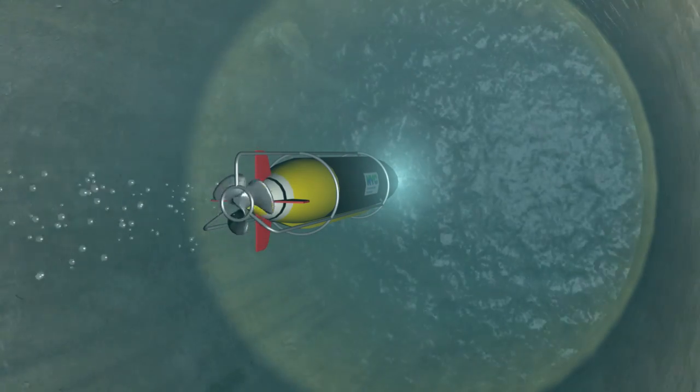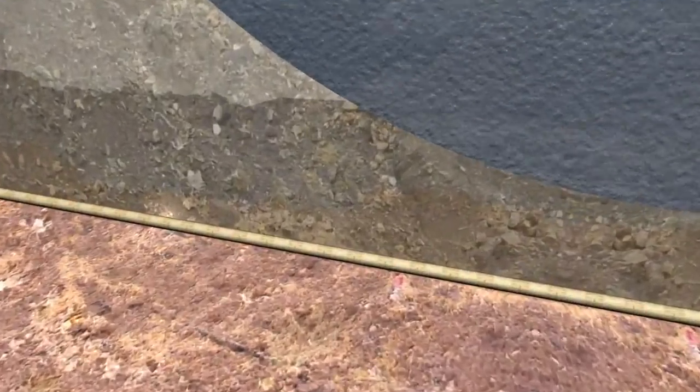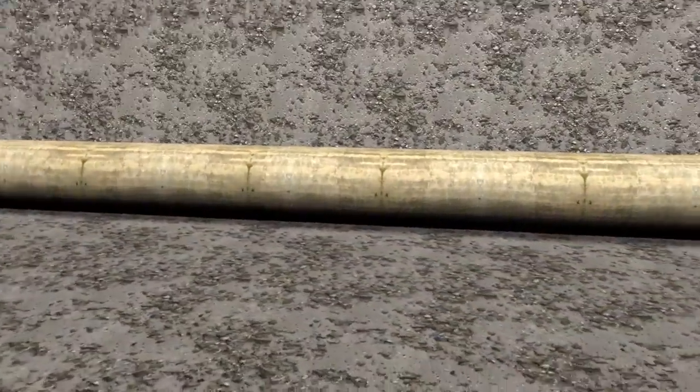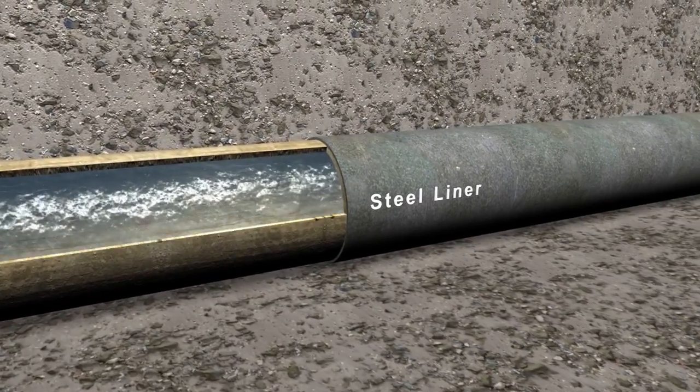To investigate further, DEP performed tunnel inspections from the inside by sending in an automated underwater vehicle. And what they found were two locations with significant leaks — one in the town of Wawarsing and the other in Roseton. But what caused these leaks? During construction of the aqueduct, the tunnel passed through areas of poor quality rock. To reinforce the aqueduct at these locations, a steel liner was built into the frame of the tunnel.